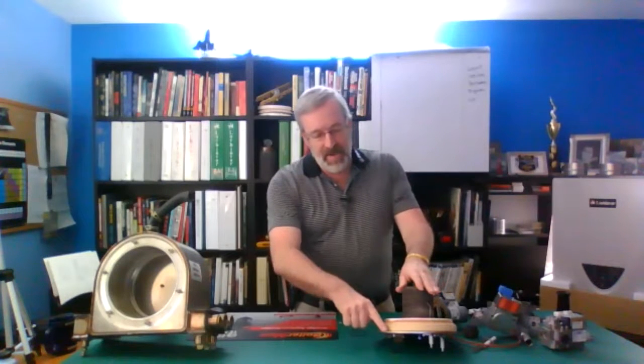Question about the temperatures that these gaskets can see. On the fire tube, those gaskets are really on the water-backed side of it. So when we're in there, we're protected by here. Really what we're seeing is the water temperature side of there generally. Because that gasket is up here, it's kind of protected by this. So basically that's what we're going to see, the water temperatures kind of into our gaskets there on that side.